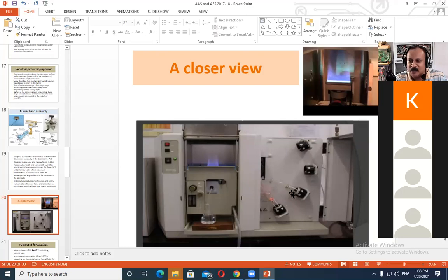These are the hollow cathode lamps. And there is what is called a turret assembly here. The spelling of this word is TURRET. The turret assembly is where we can put multiple lamps in the lamp holders, and these lamp holders are given numbers 1, 2, 3, 4, and so on. At a time, maybe 6 to 8 different lamps can be placed inside.